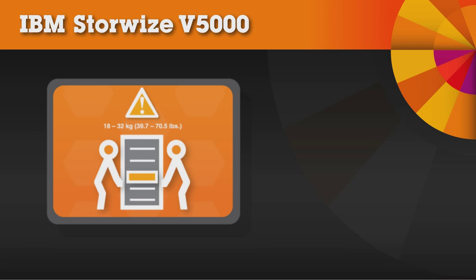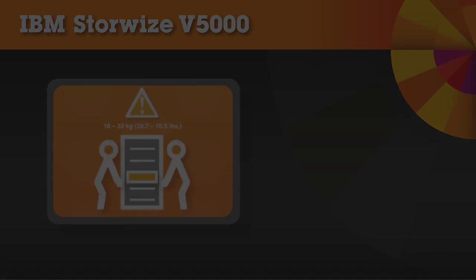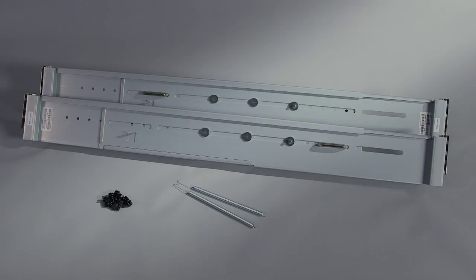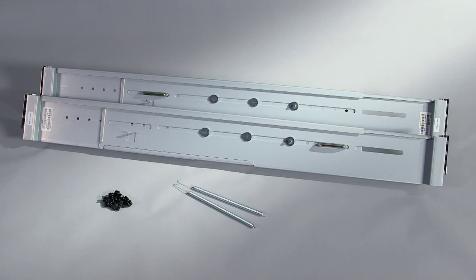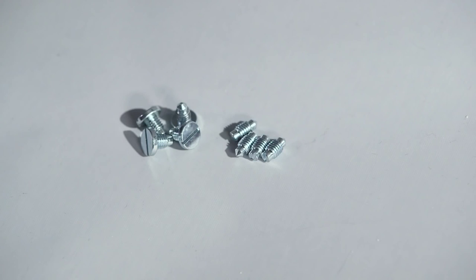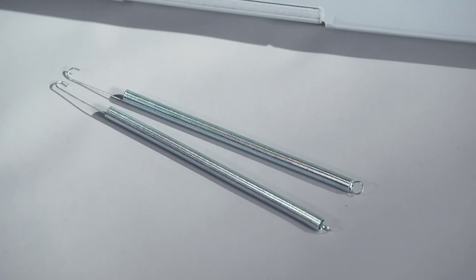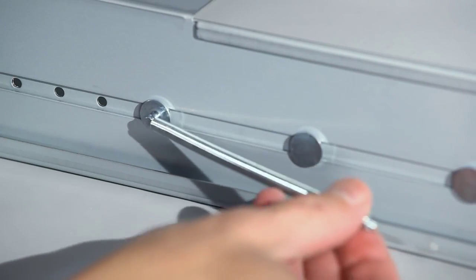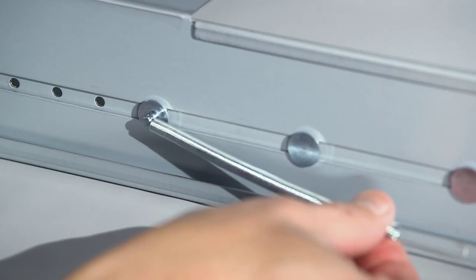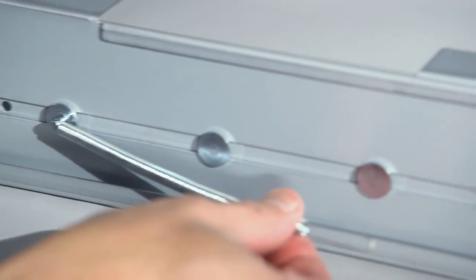Let's begin. Each rail comes with a set of support springs and mounting screws. Alternative mounting pins are also included for non-IBM racks, so swap them out if necessary. Begin installation by attaching the support rail springs. Attach the circle end of the spring around the stud on the rail.